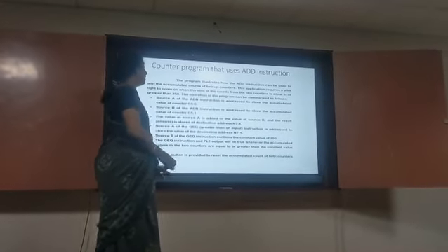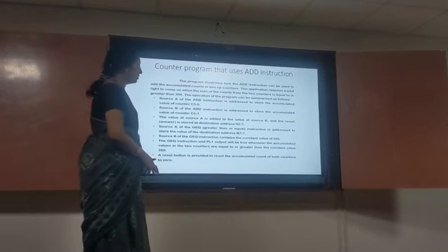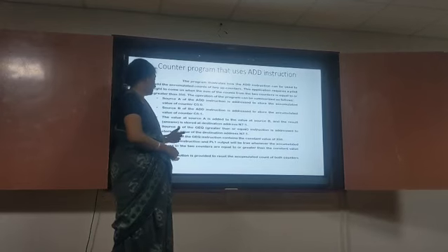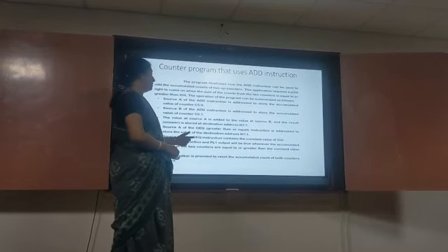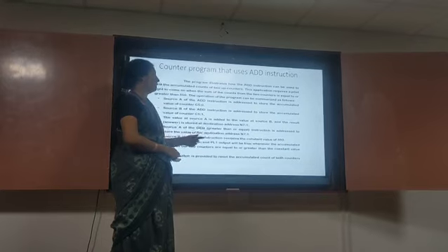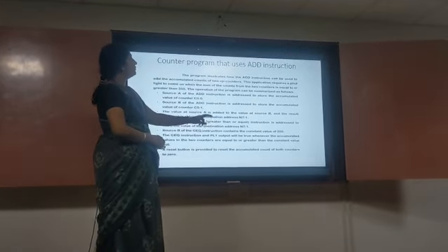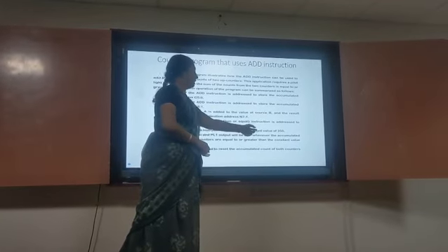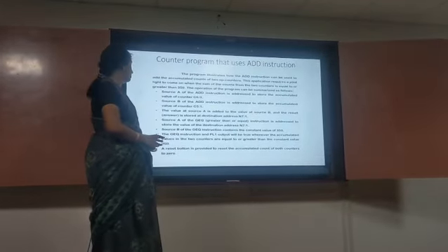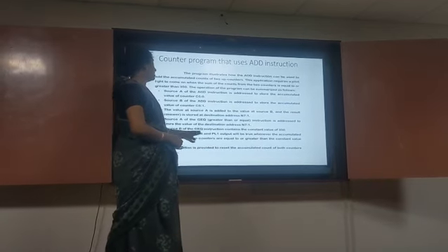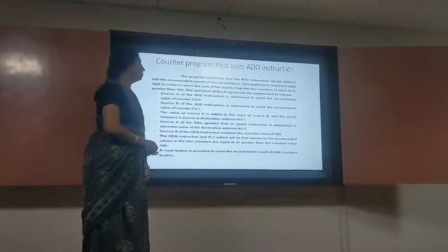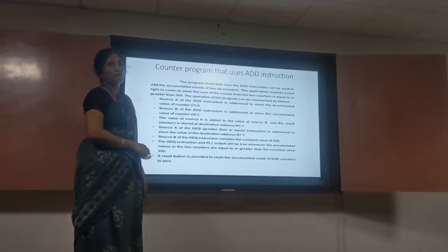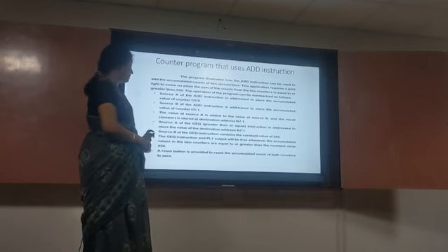Source A of the GEQ, greater than or equal to instruction, is addressed to store the value at the destination address N7:1. Source B of the GEQ contains the constant value of 350. So 350 is the count that we require, which can vary according to your program. The GEQ instruction and PL1 output will be true whenever the accumulated values in the two counters are equal to or greater than 350, which is the value that we have set.